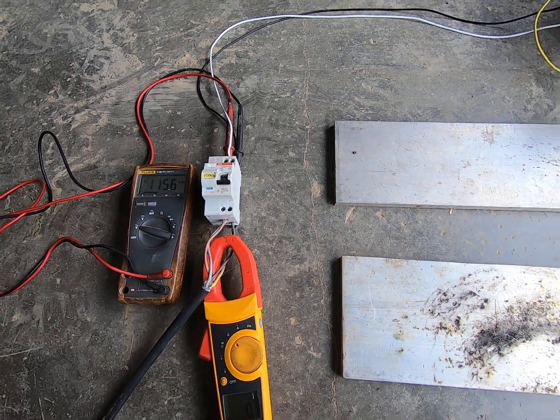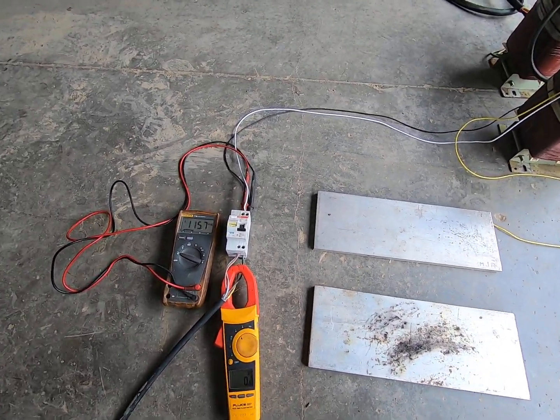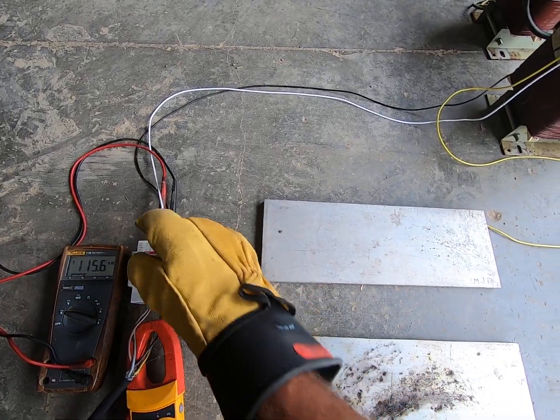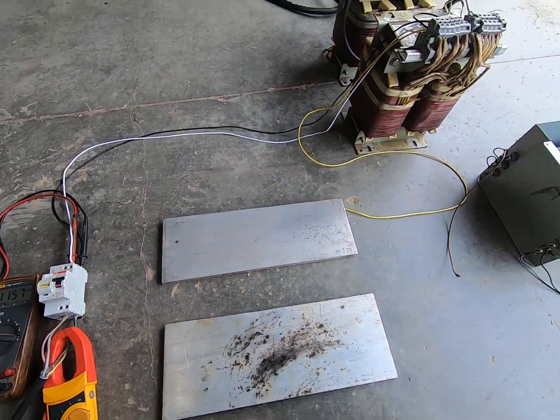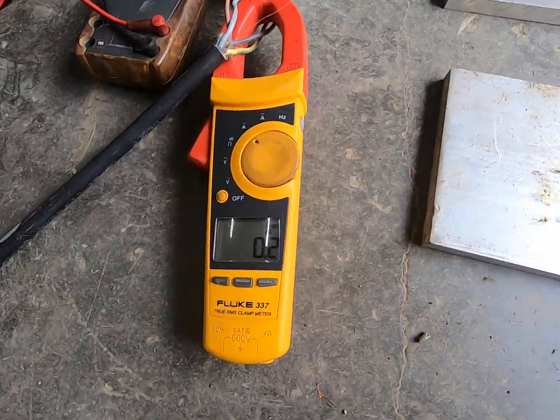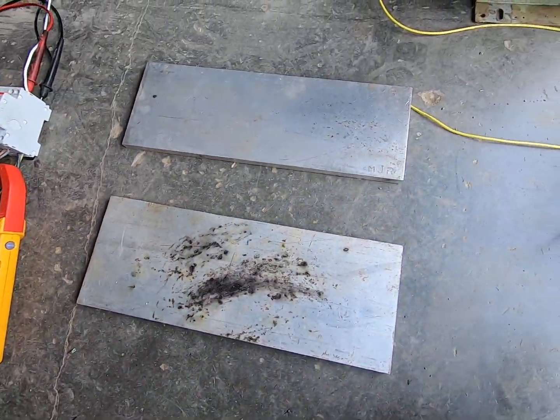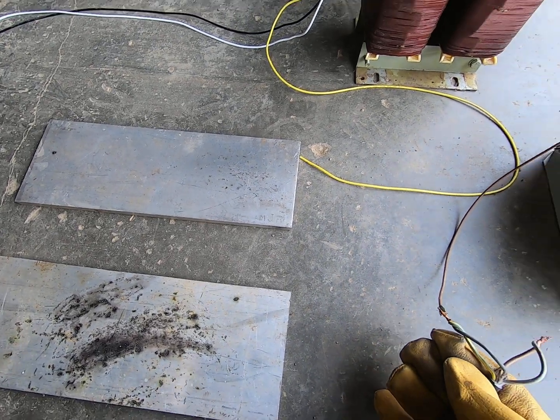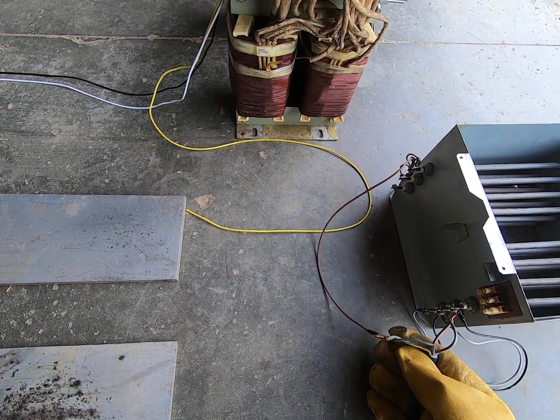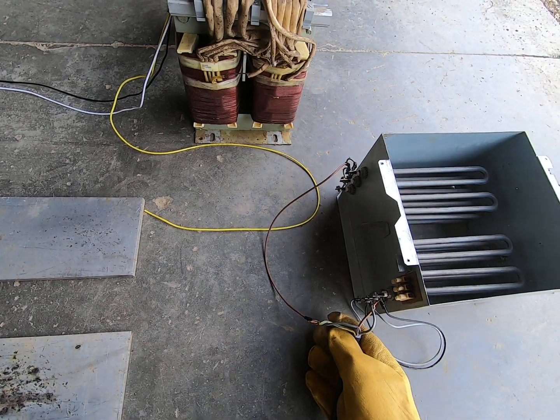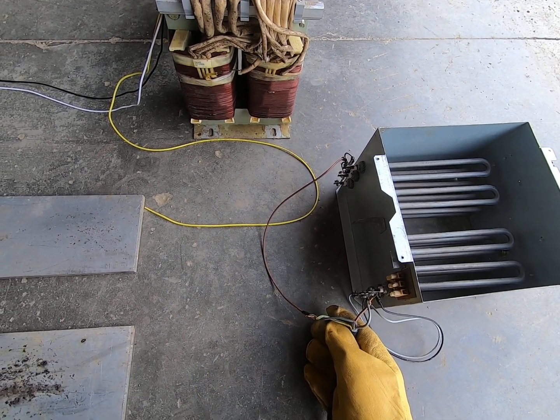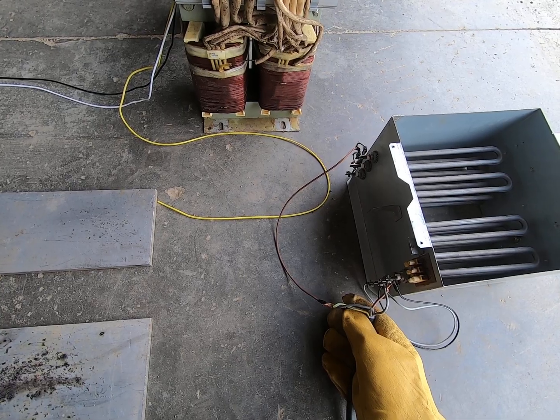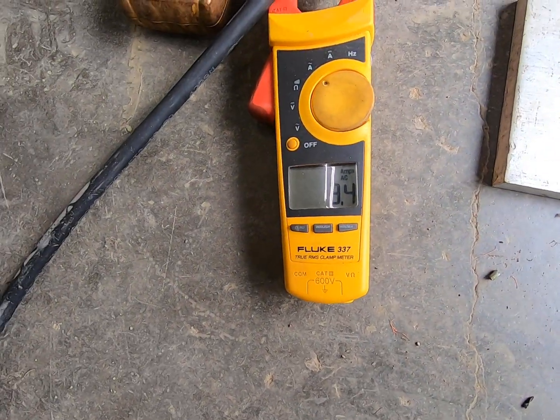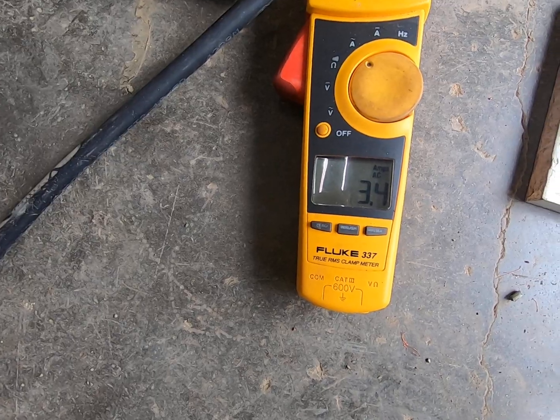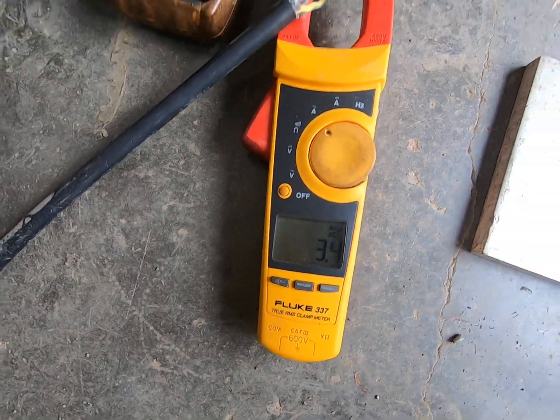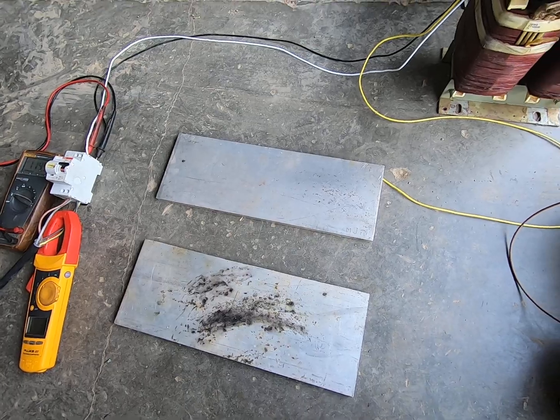That works as expected. Now, another test we can do, I can put a small load on this circuit just to check my amp clamp here. I've got 0.2 amps, which effectively is 0. If I attach this heating circuit, or this heater assembly to the circuit, the heaters are in parallel. There's roughly 32 ohms. Should be about 3.75 amps, and I'm getting about 3.4. Everything's normal as far as that goes.